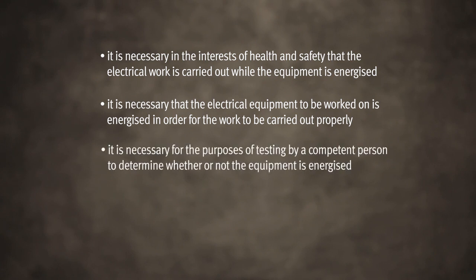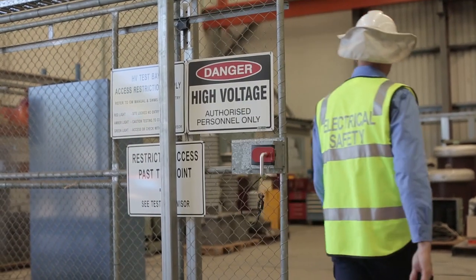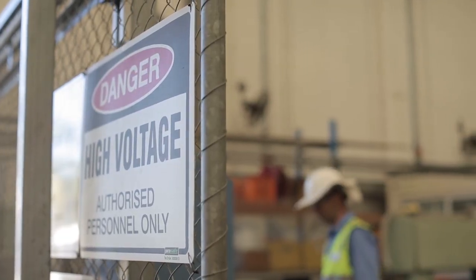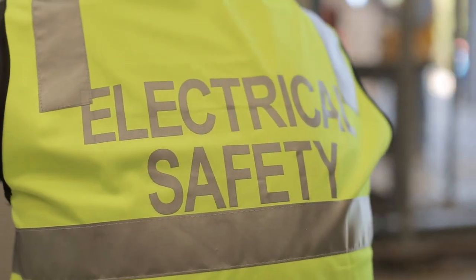Or, it is necessary for the purpose of testing by a competent person to determine whether or not the electrical equipment is energised, or there is no reasonable alternative means of carrying out the work. You can also examine the fault current limit of the installed local and upstream protective devices. If you have any doubts regarding your safety or that of the installation, confirm with the manufacturer that sufficient protection exists. If your investigation reveals inadequate protection, advise the owner both verbally and in writing of the hazardous situation.